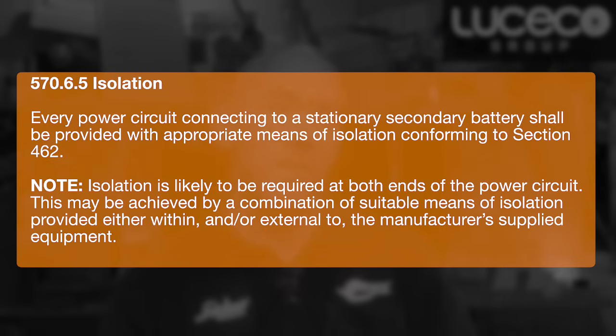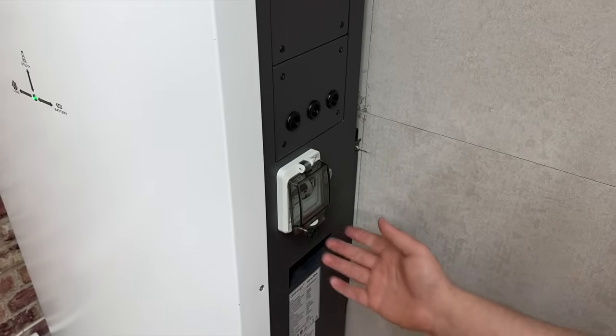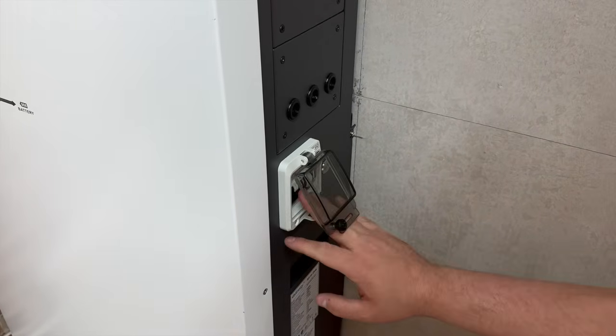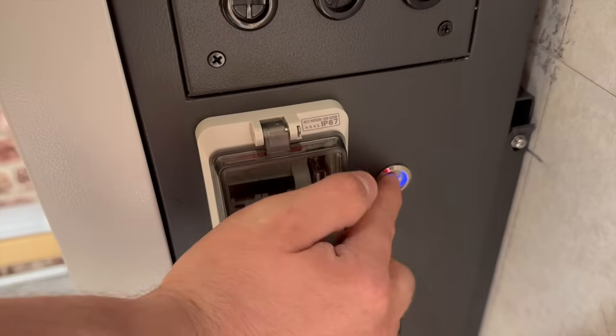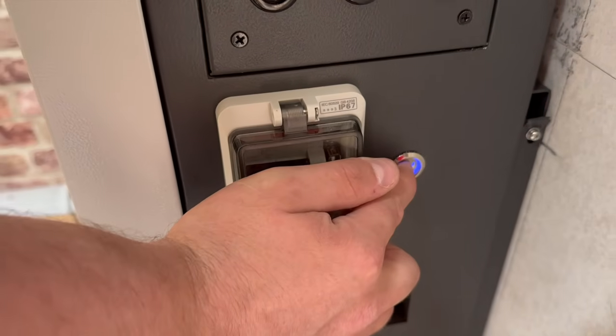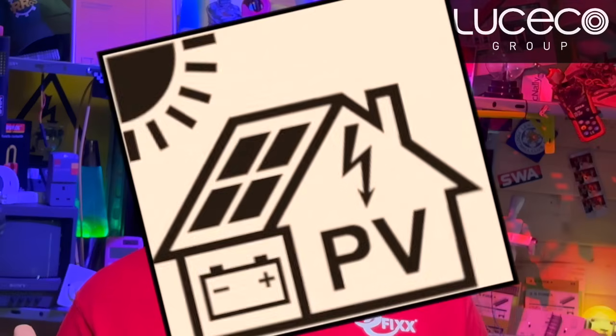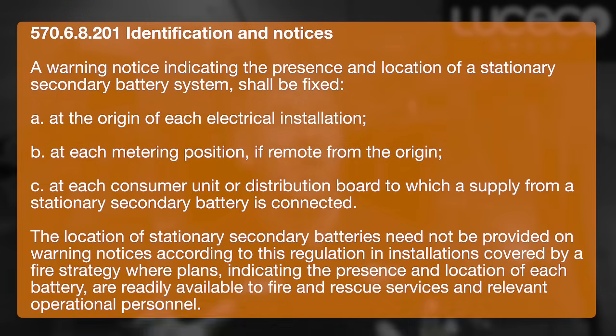Regulation 570.6.5 requires a means of isolation for the battery system, because even if you disconnect the main supply, the battery can still energize the installation, so you cannot assume the system is dead just because the main switch is off. And finally, labeling. It's back! Regulation 570.6.8 requires a warning notice to indicate the presence of a battery system.